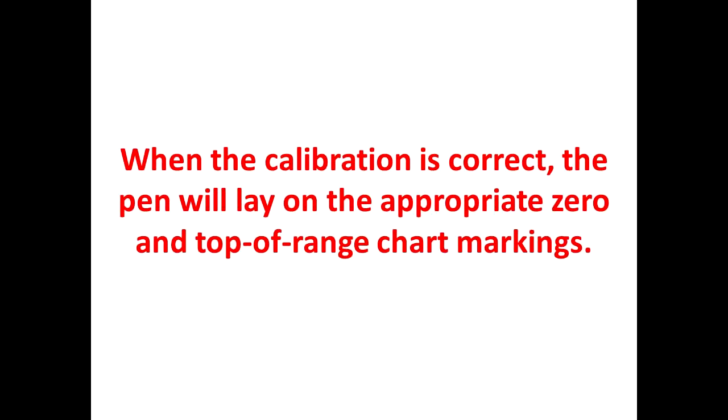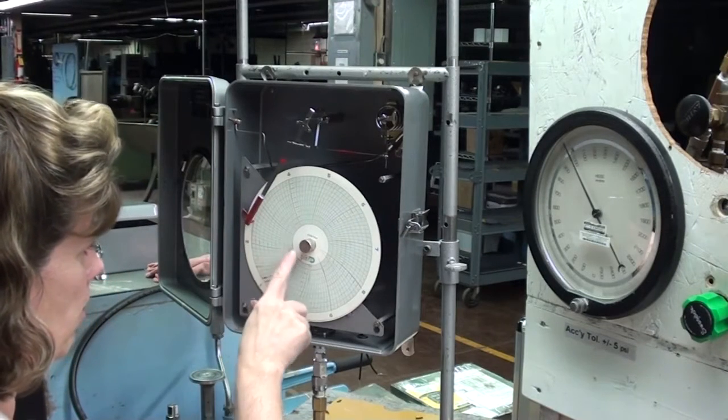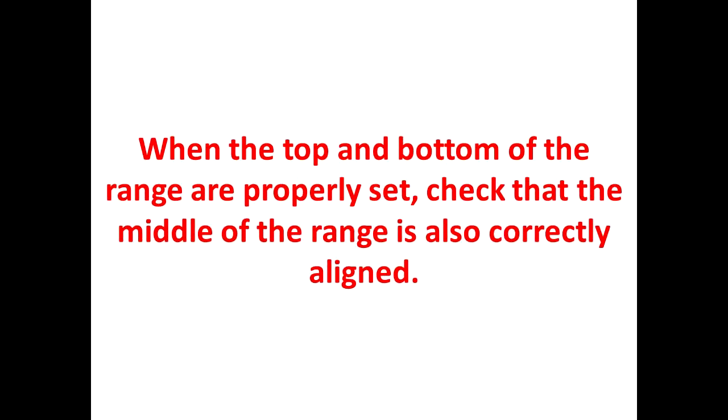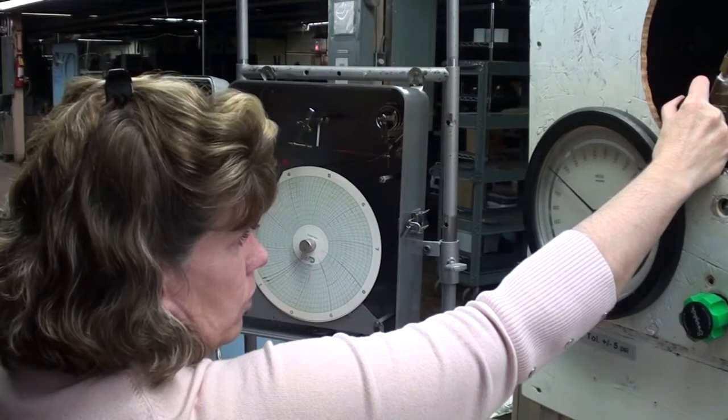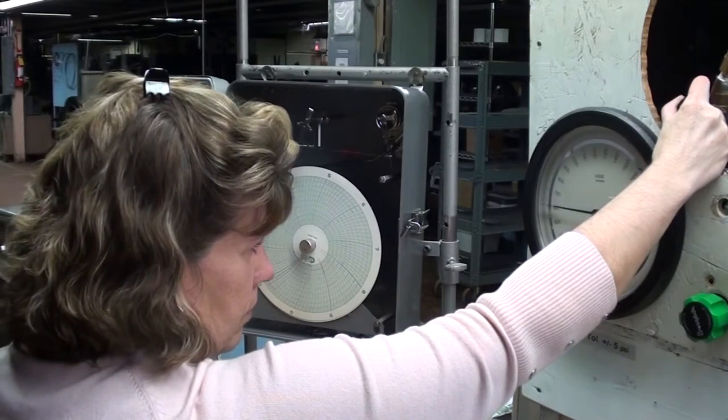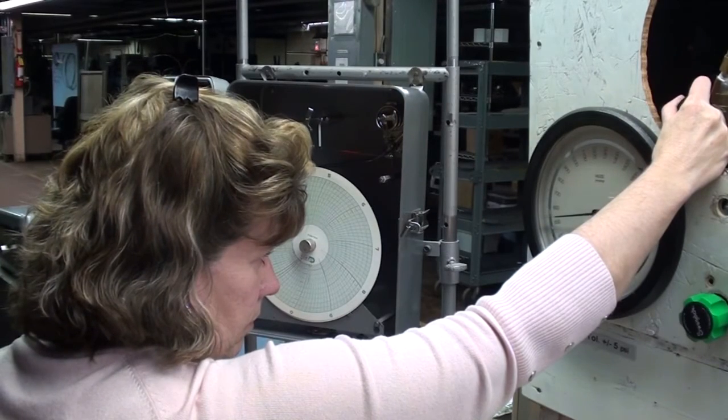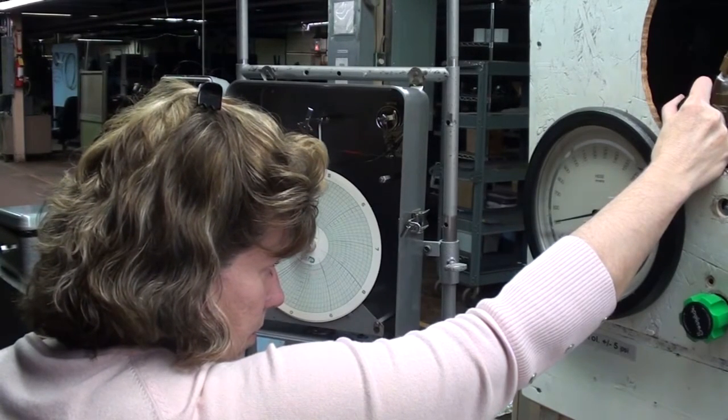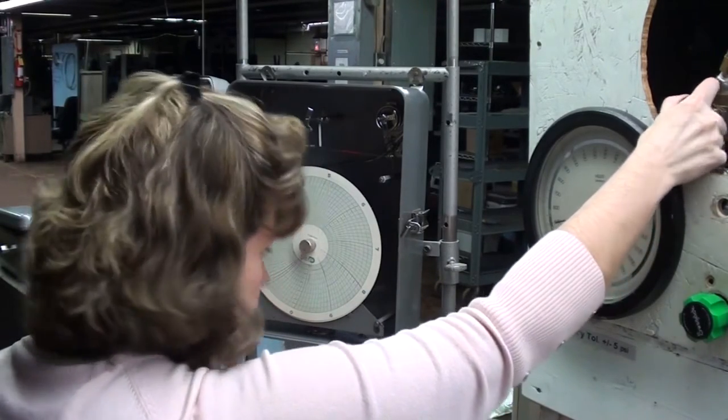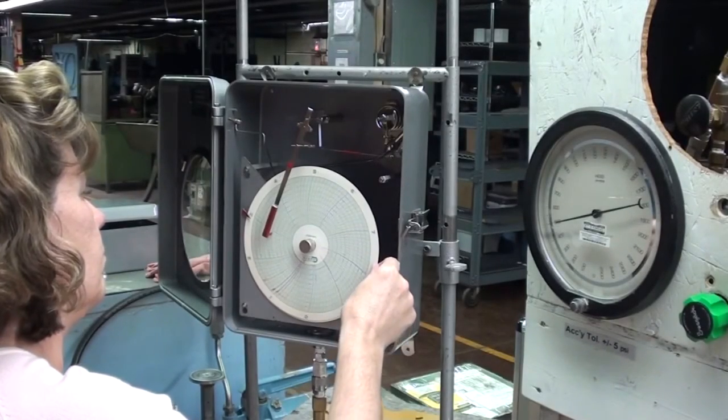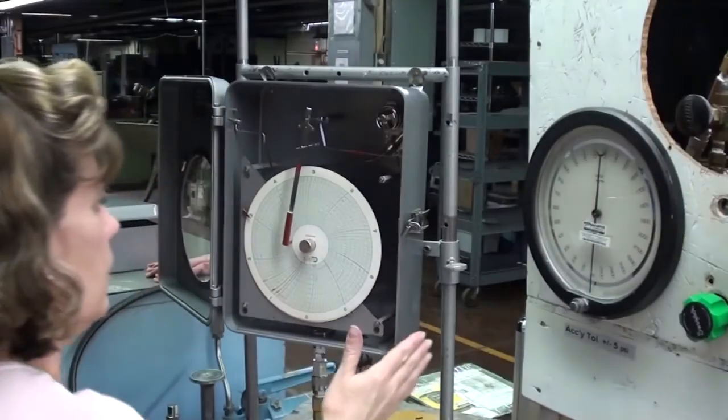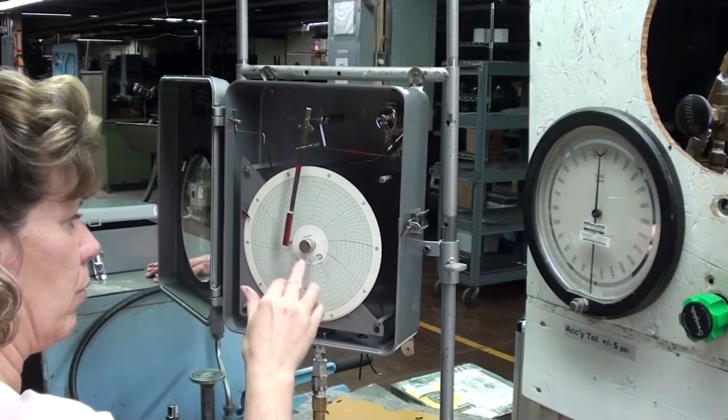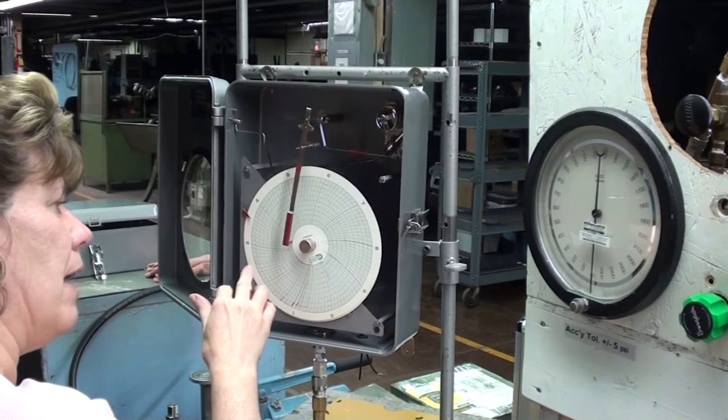Okay, we're calibrated. This is a zero to 1,000. We're at zero here, and we're at 1,000 at the top. Now, let's check a midpoint on the charts. We're at 500 psi. And we're at zero. When we calibrate, we do zero, we do the middle going up, top, and then the middle coming down.